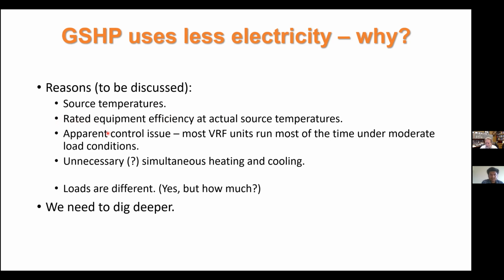And then we have this apparent control issue with the VRF units running most of the time, even under moderate load conditions. I'll say unnecessary simultaneous heating and cooling, but I guess you could say that's arguable. Maybe it's really necessary to heat in one zone and cool in the zone next to it to maintain some user desired temperature. And then of course the loads are different, but how much different are they? We need to dig deeper into that, and that's what the rest of the study goes into, these details.